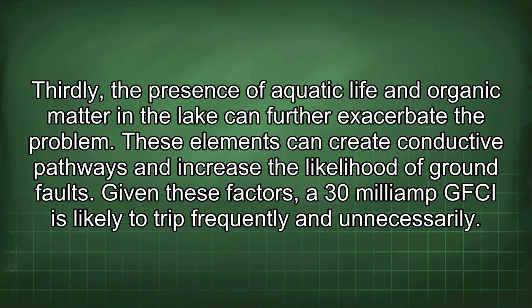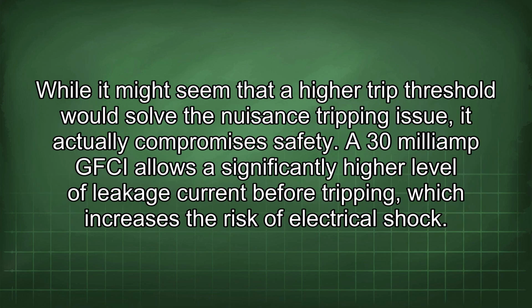Thirdly, the presence of aquatic life and organic matter in the lake can further exacerbate the problem. These elements can create conductive pathways and increase the likelihood of ground faults. Given these factors, a 30 mA GFCI is likely to trip frequently and unnecessarily. While it might seem that a higher trip threshold would solve the nuisance tripping issue, it actually compromises safety.